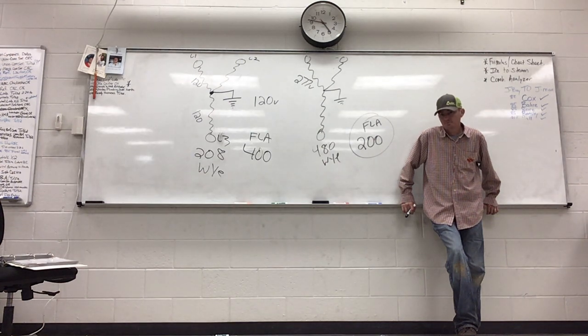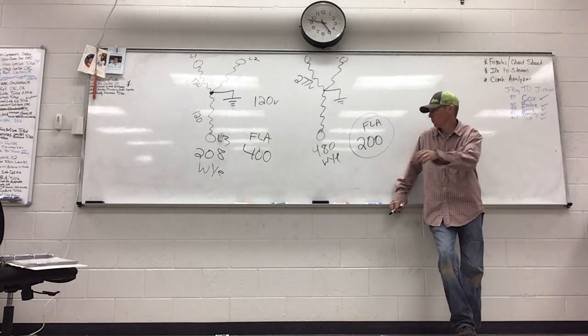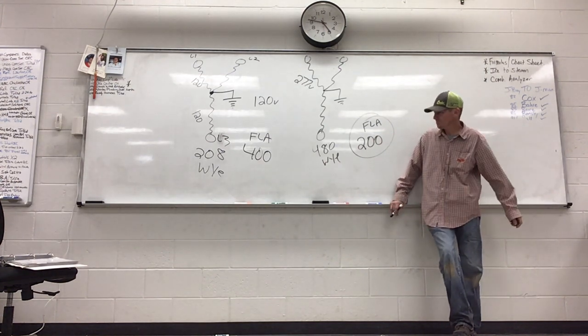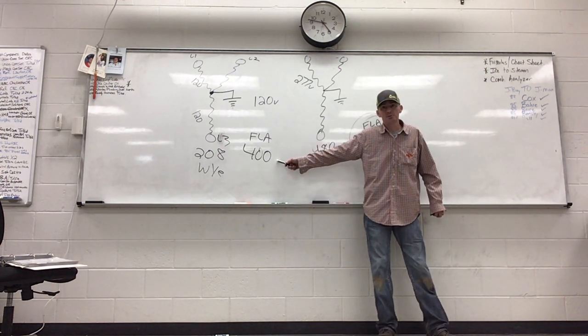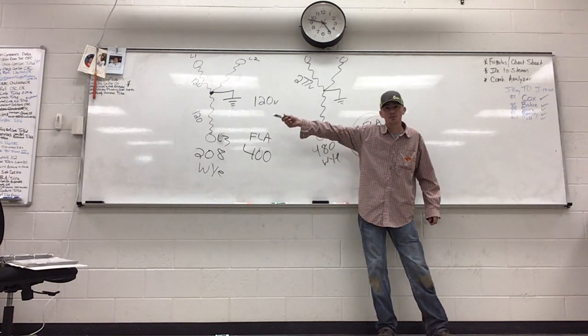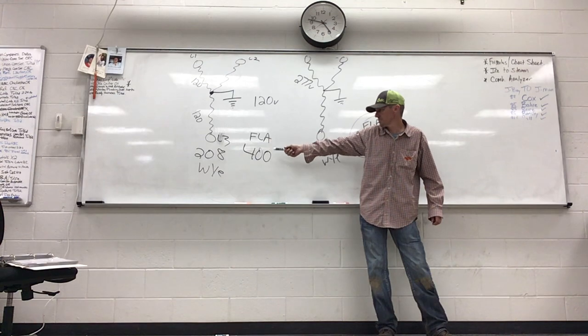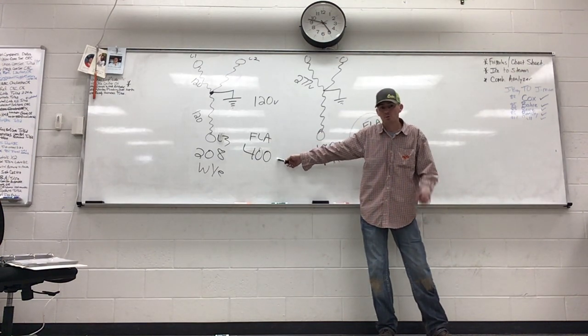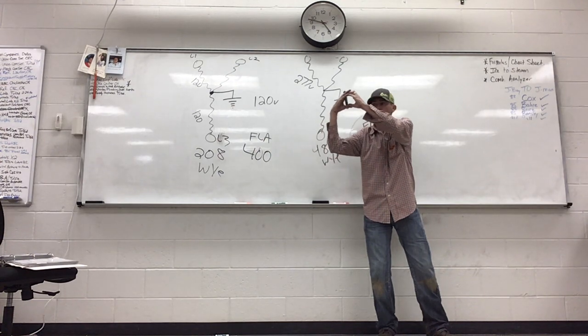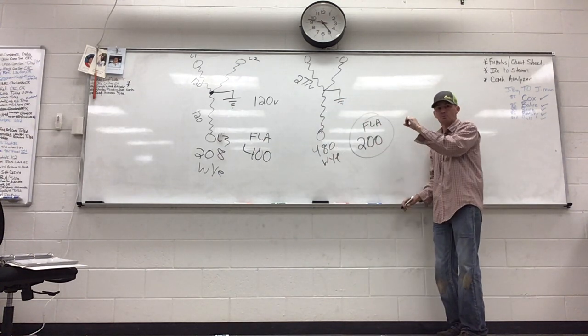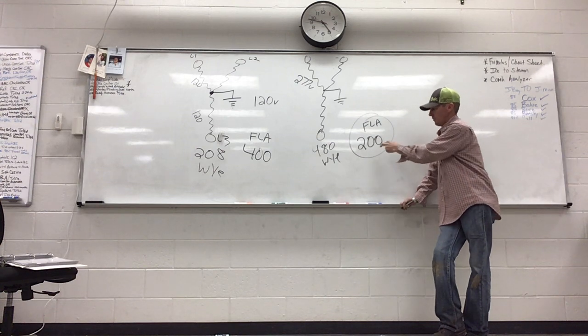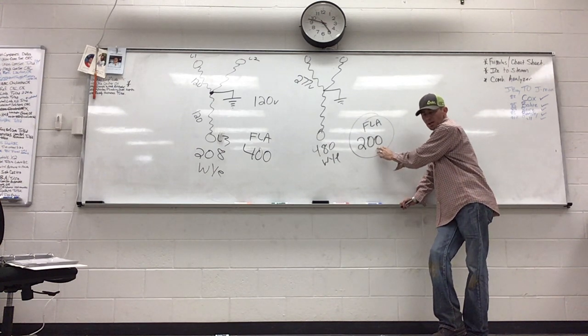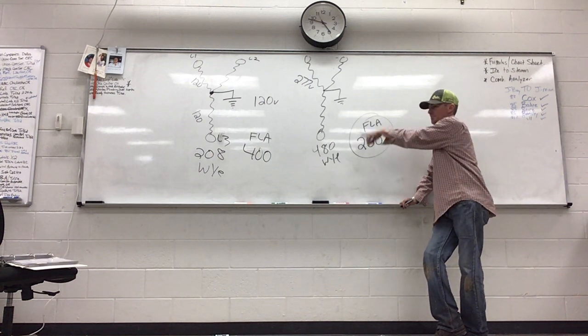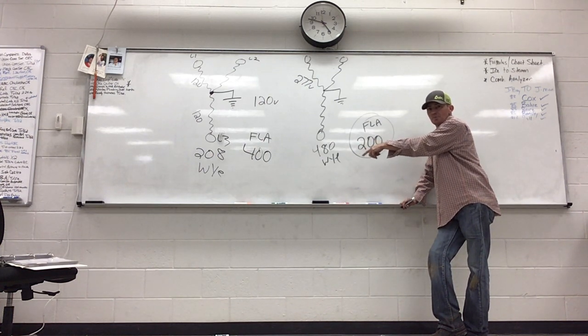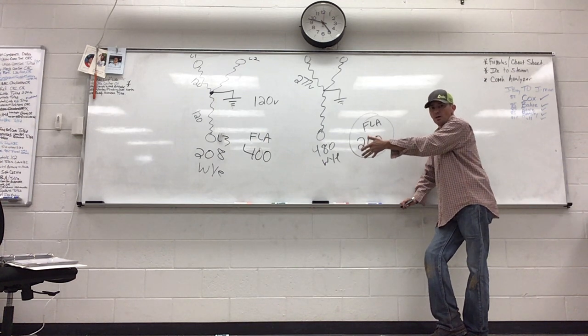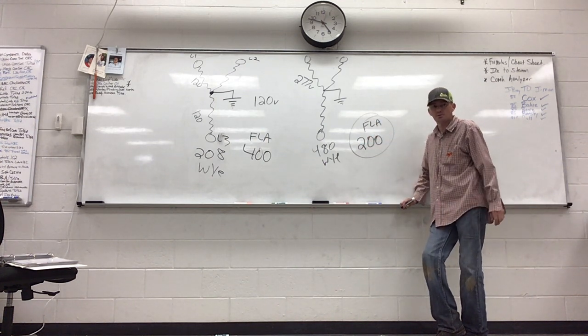And that's a good thing because now we can run smaller wire to feed this stuff. If the electricians are pulling wire out to a screw machine sitting outside, I don't want to pull this wire. I hope you guys can see. I don't want to pull that wire. I'd rather pull this cheaper wire, right? So the cost of the wire savings has to compensate and override the cost of those additional transformers and such that you're going to have to buy just to knock this down to 120 volts, right?